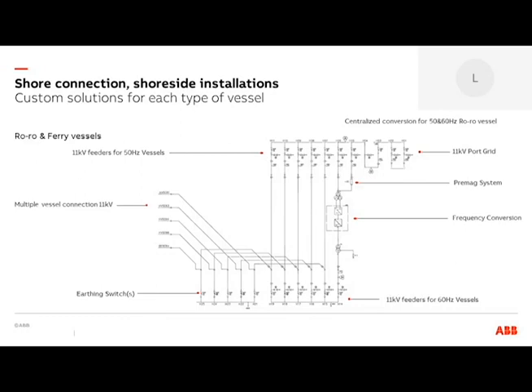Another characteristic of this sort of vessel is that they connect daily. So this topology is also achieving a sort of heavy-duty operation. Each function, that is the connection to the 50 or to the 60 hertz and the grounding of the shore connection for safety reasons when it's not in operation, is achieved through a dedicated device, a dedicated earthing and disconnector switch.